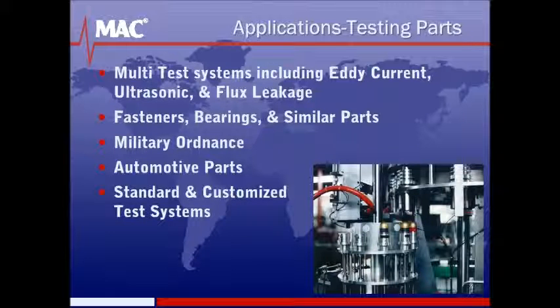MAC eddy current and electromagnetic test systems are available to test fasteners and similar parts for heat treatment, geometry, and alloy. The systems test and separate out parts that are either above or below specification from those that conform. This test can be done at very high speeds using MAC's Auto Sort Parts Gate and Varimac Comparator Tester. Customized parts testing using multiple test technologies have been developed for inspecting military shell bodies, grenades, bearing races, and automotive parts such as pistons and strut rods, among others.